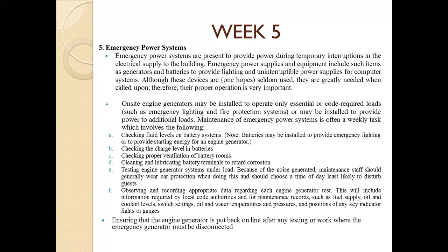Okay? So meron din tayo mga preventive maintenance na ginagawa for our generators. Okay? Checking fluid levels on battery system, checking the charge level in batteries, checking proper ventilation for battery rooms, cleaning and lubricating battery terminals to retard corrosion, testing engine and generator system under load, observing and recording appropriate data regarding each engine generator test. So yun yung mga standard na ginagawa.